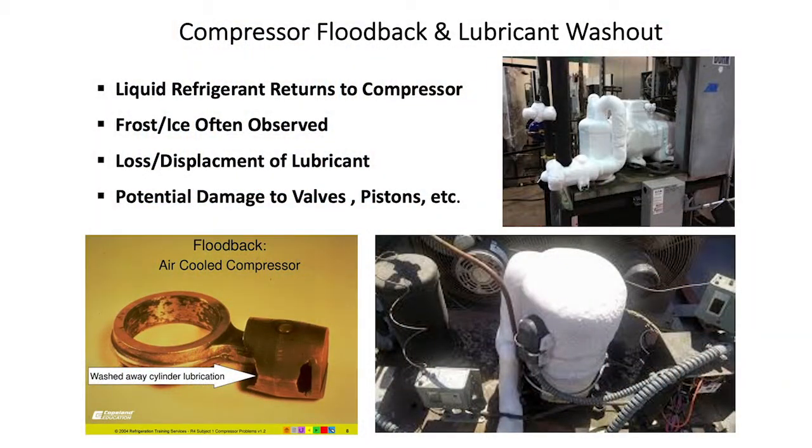Let me talk about a situation that can occur when a system isn't operating properly while running: flood back and wash out. Flood back refers to liquid refrigerant flooding back into the compressor. Compressors are designed to handle vapor, not liquid — liquid isn't compressible and can result in broken valves and broken pistons. As it relates to the lubricant, liquid refrigerant can wash out lubricant and leave bare metal where bearings and moving parts are supposed to be, and machines won't operate well or long without lubricant.